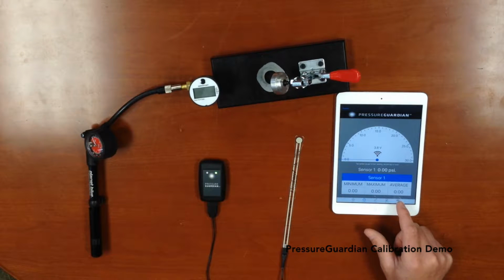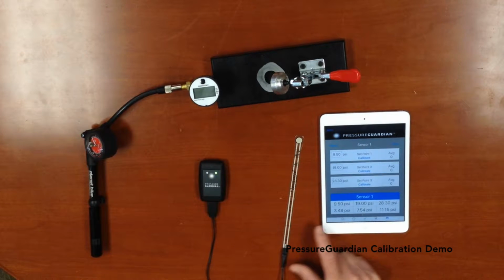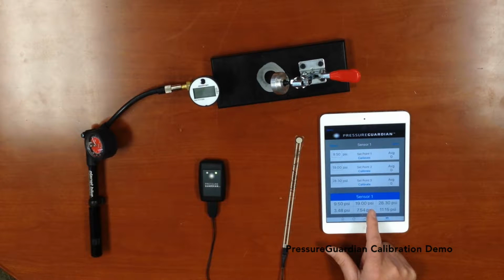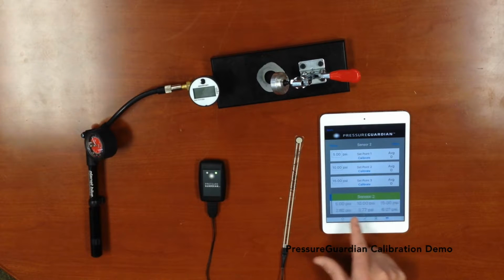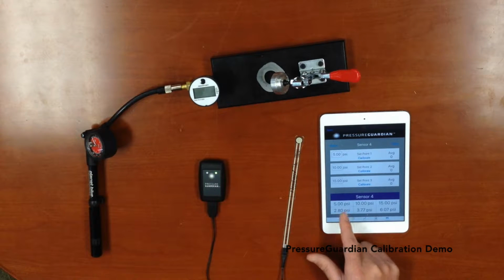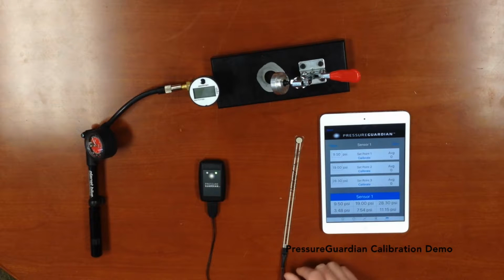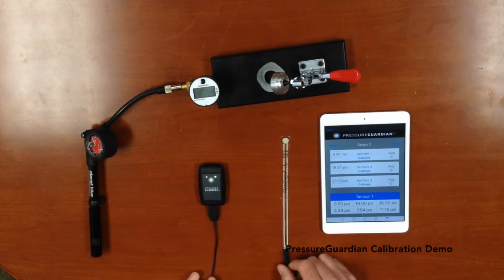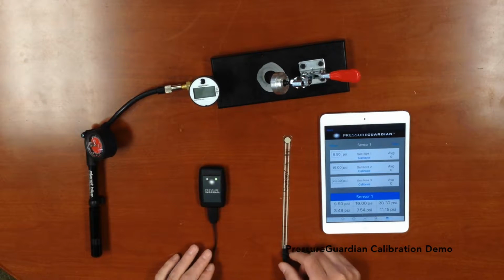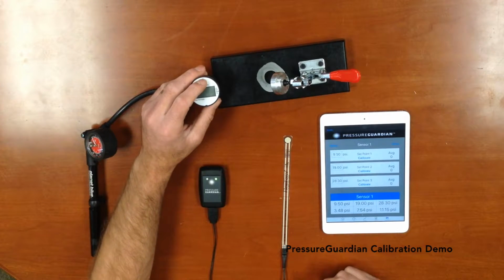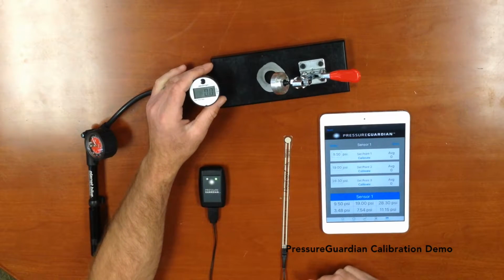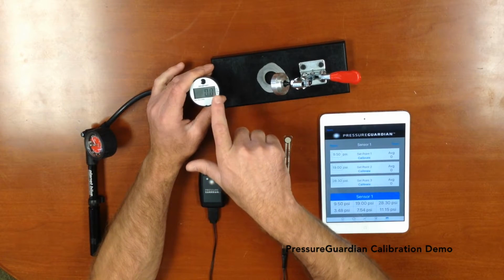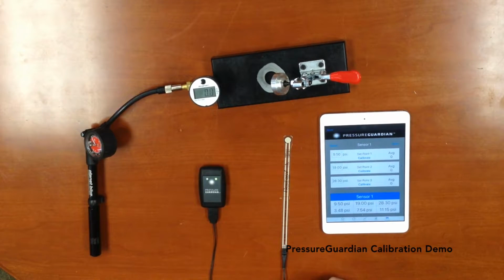Now we're going to go to our calibration screen. So I want to make sure I'm on sensor 1. If I have multiple sensors, I can swipe to sensor 2, 3, and 4. But we're going to start with sensor 1 since I'm only calibrating a single lead system. We're going to turn the calibration jig on, and there's a real small arrow up in the top right hand corner. We want to make sure that arrow is pointing to PSI and not one of the 3 other measurements.